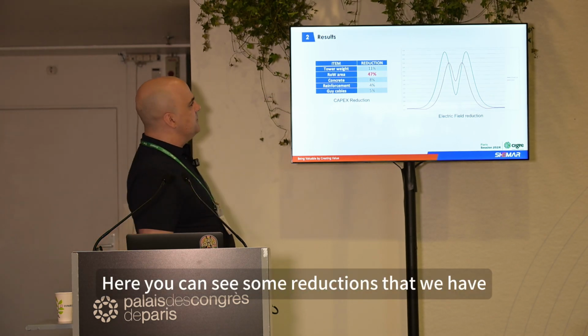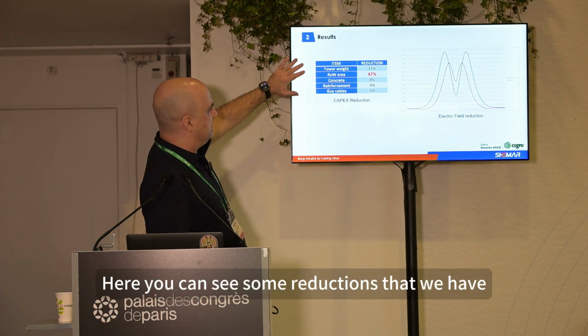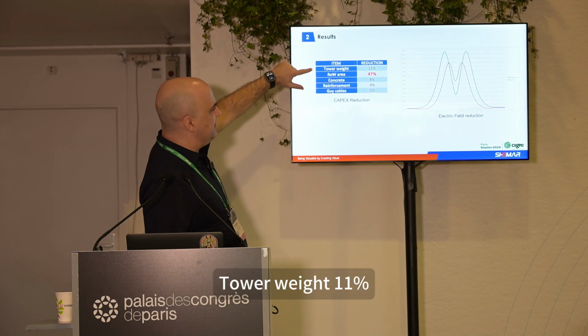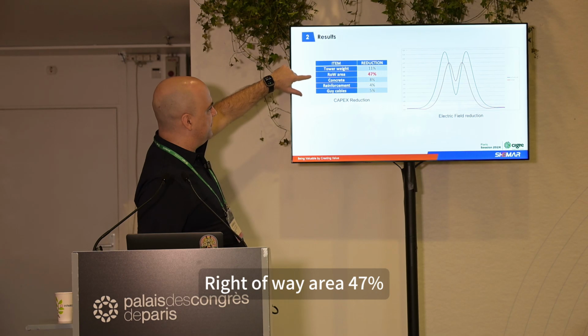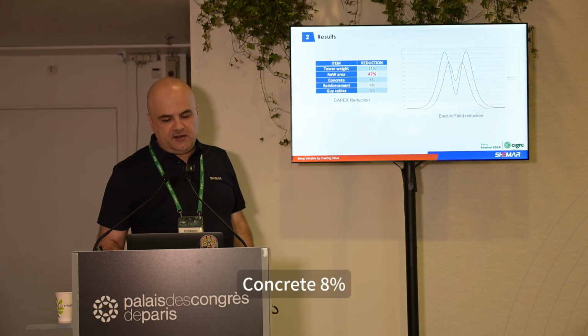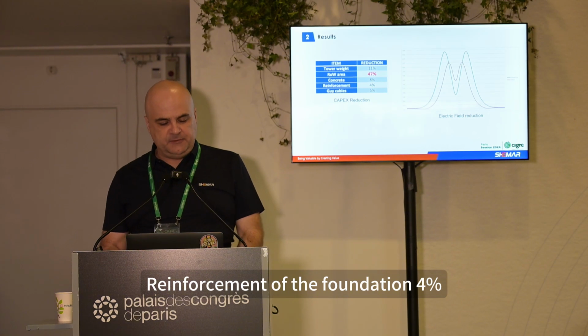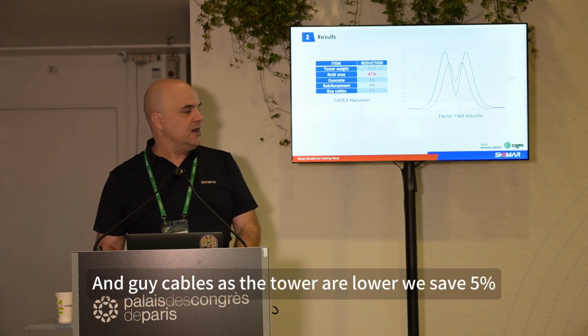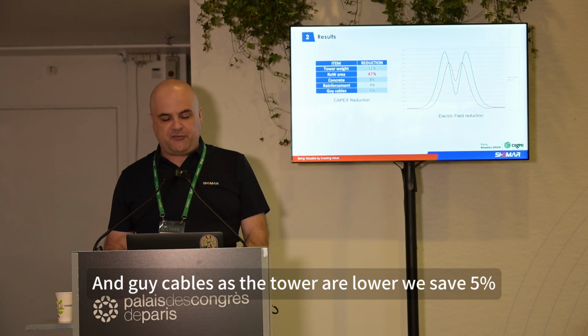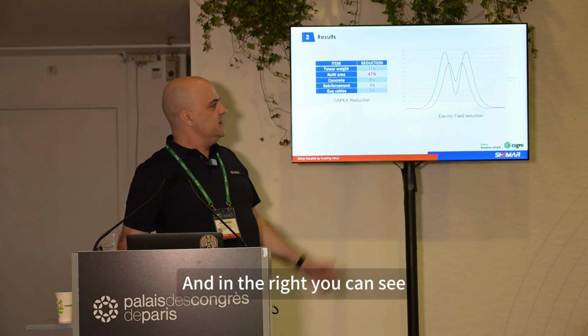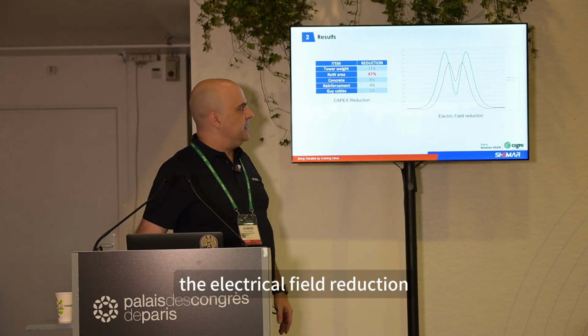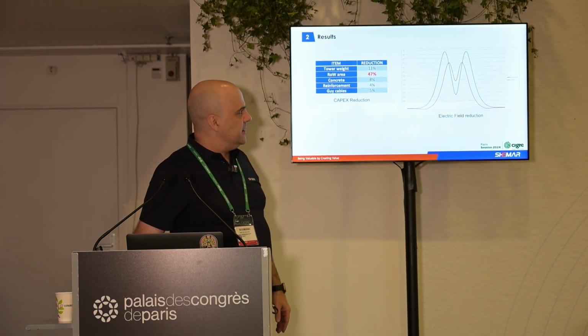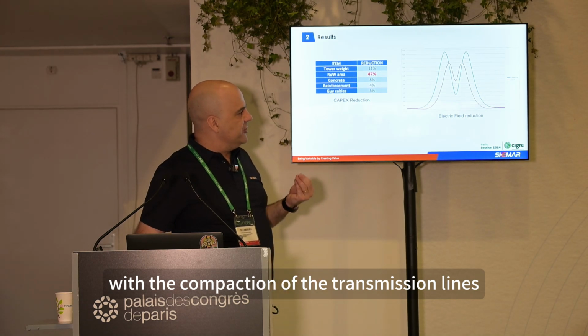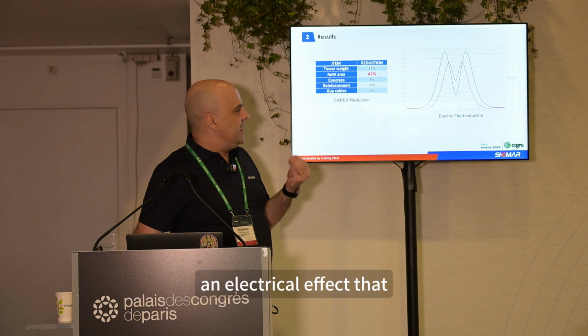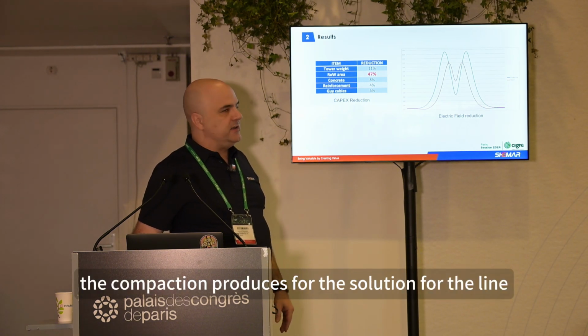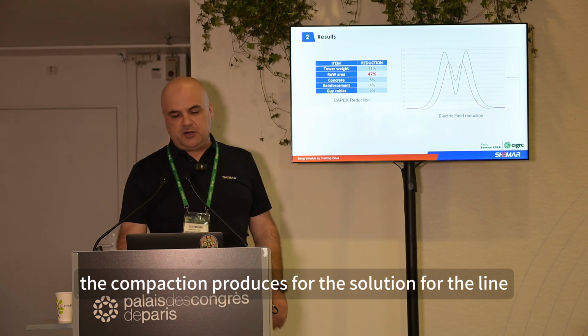Here you can see some of the reductions we achieve: tower weight 11%, right-of-way area 47%, concrete 8%, foundation reinforcement 4%, and guy cables 5% savings since the towers are lower. On the right you can see the electrical field reduction obtained from the compaction of the line -- an electrical effect produced by the compaction of the solution.